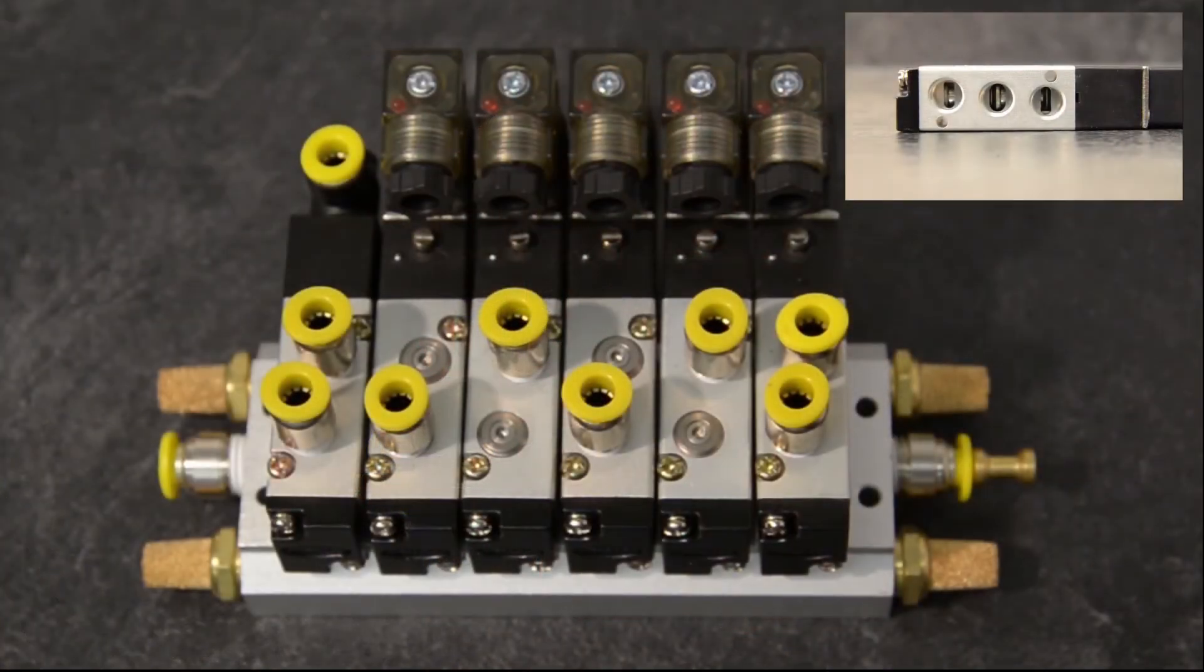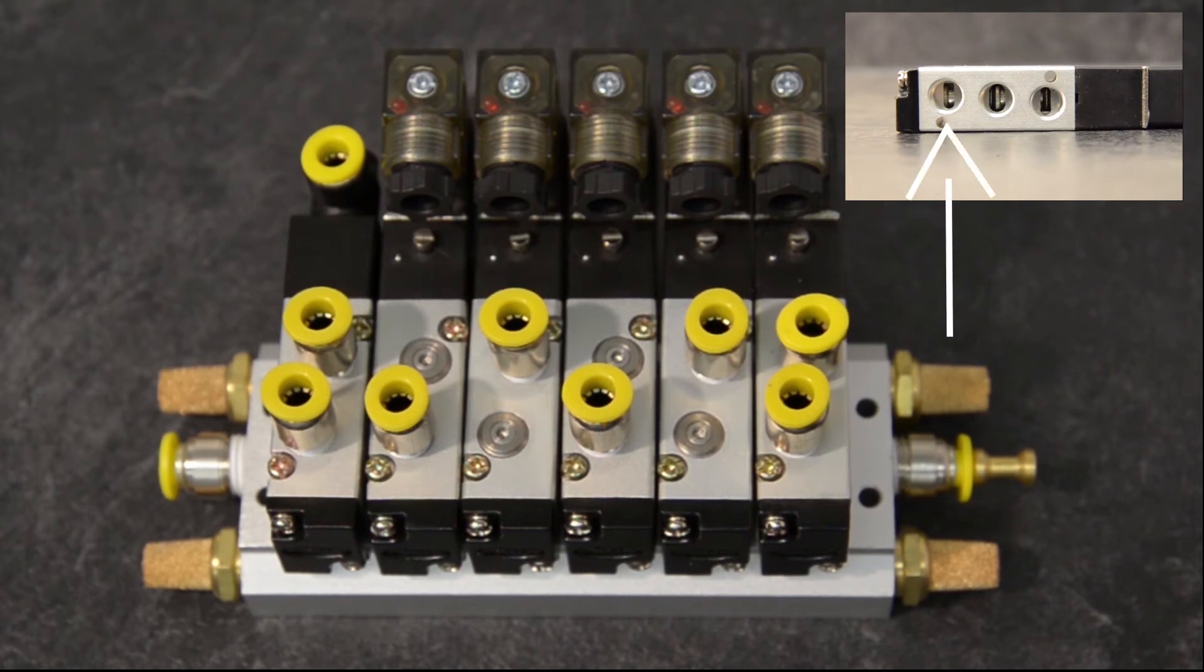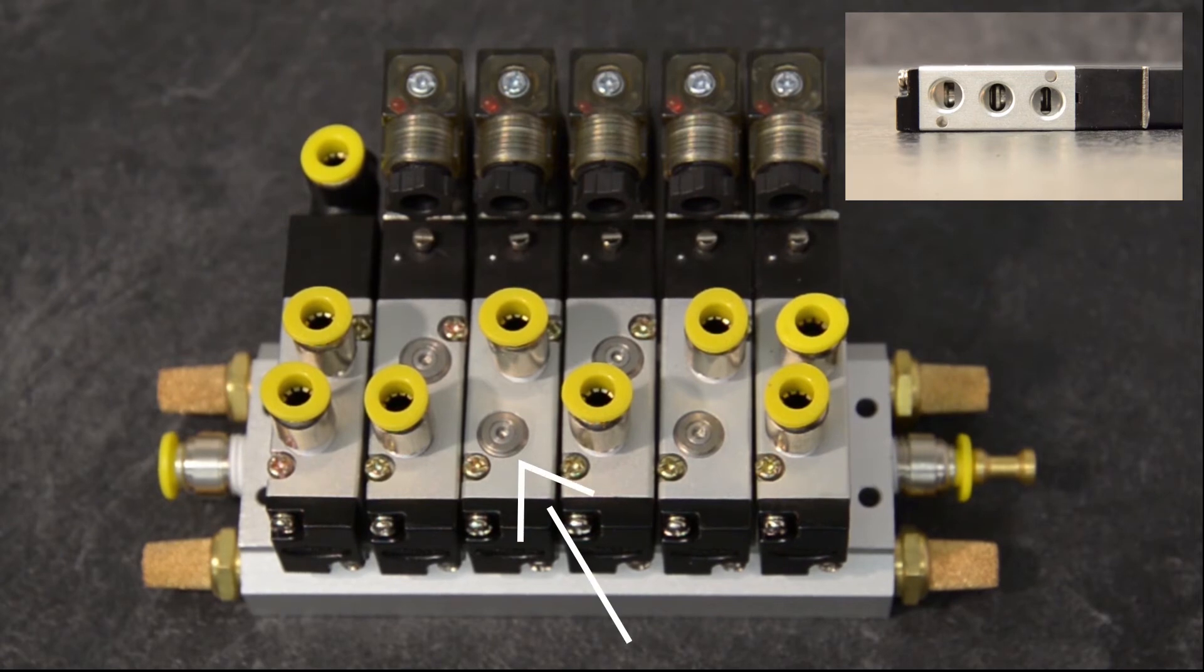In order to get a normally open two-way, we plug the B port and plug the exhaust port EA. In order to get a normally closed two-way, we plug the A port and plug the exhaust port EB.